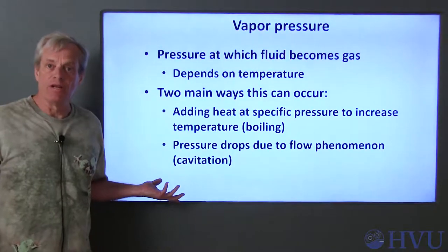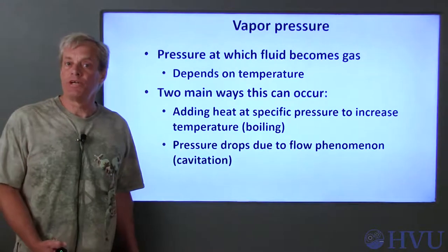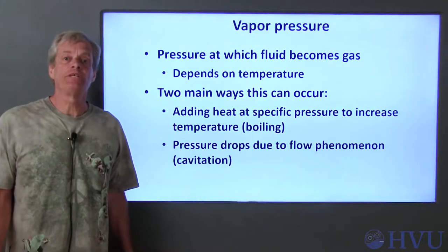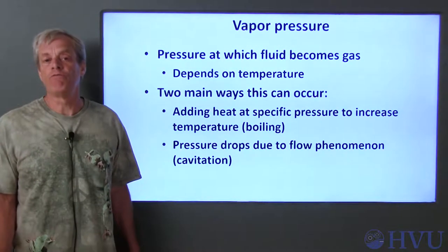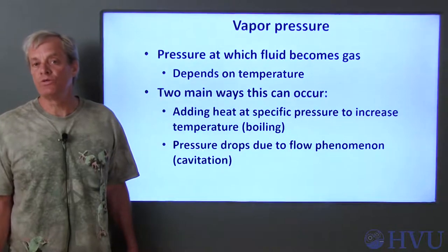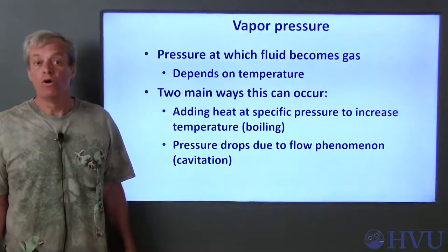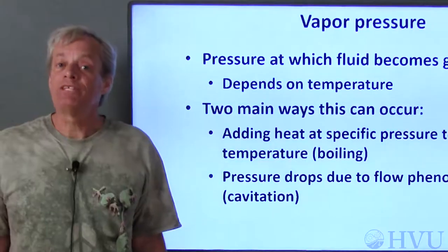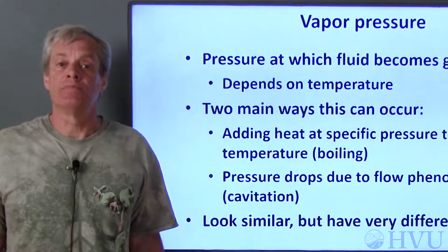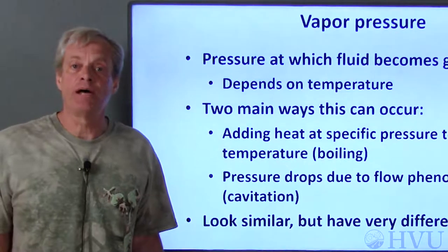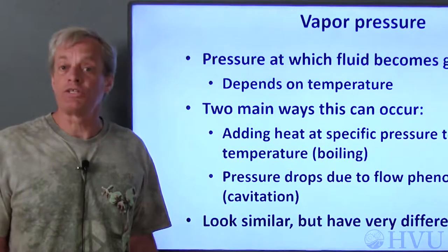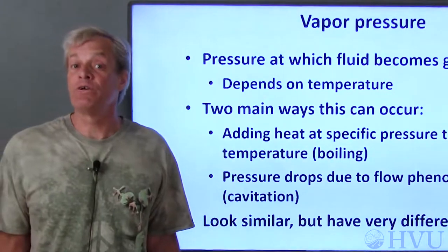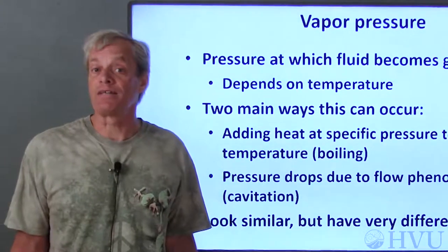If these phenomena cause the pressure to drop below the vapor pressure, we can have what is sometimes called flow-induced boiling, or more commonly cavitation. Cavitation and the bubbles caused by boiling water on a stove appear to be similar, but they can have very different effects.